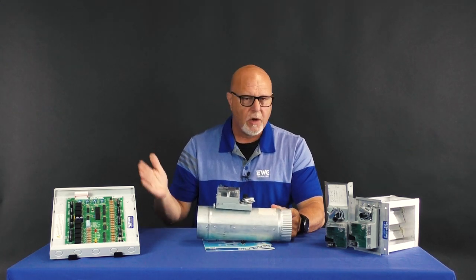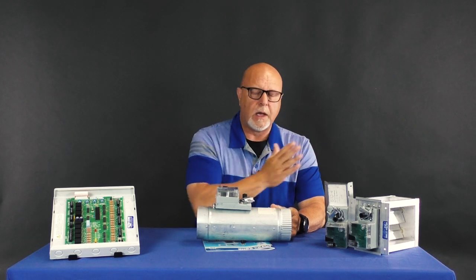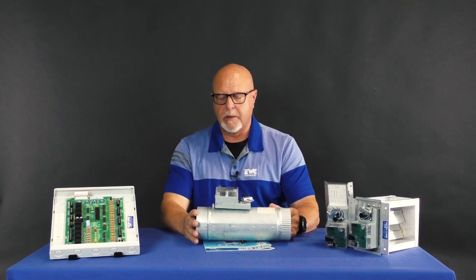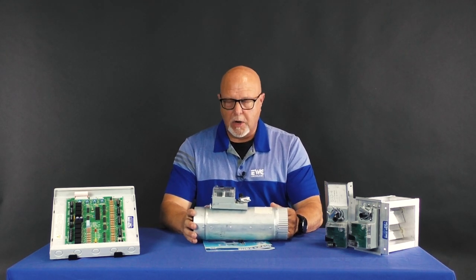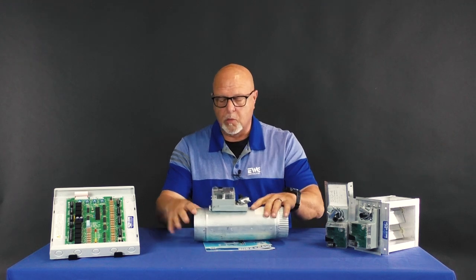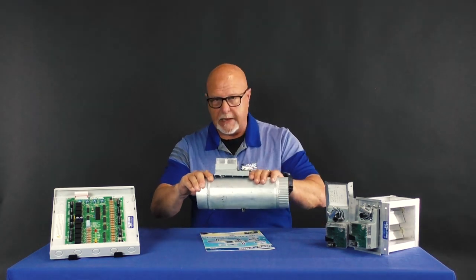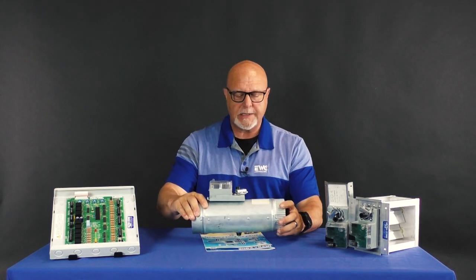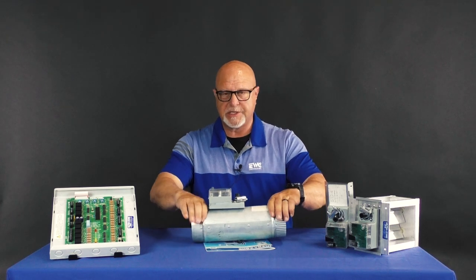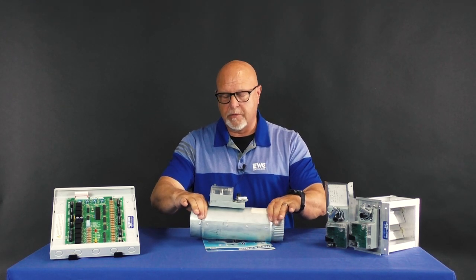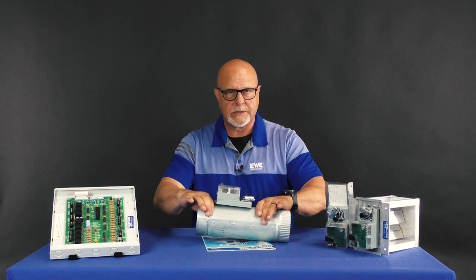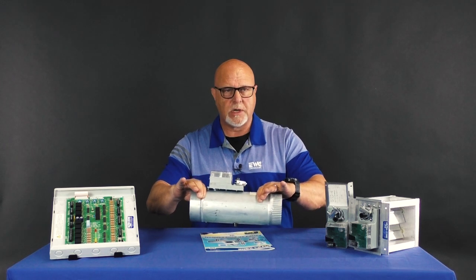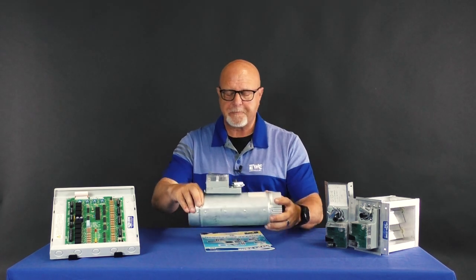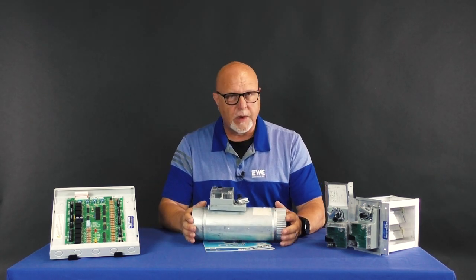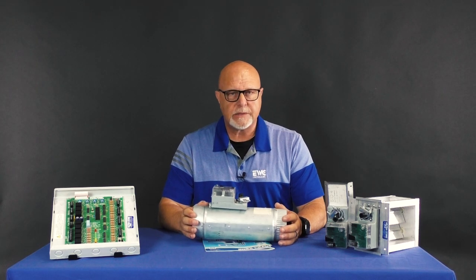This allows you to go from a start collar and continue on with your round pipe going forward, or round pipe and flex duct from here. Really doesn't matter to us because we've put stiffening beads on the round dampers that also act as something to hold the flex on with your strap. This is 24 gauge galvanized metal.